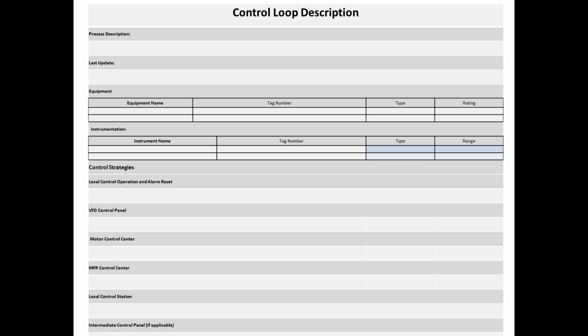The motor control center may not have anything else other than a power switch, but you say that in order for that piece of equipment to run, the power switch needs to be energized. Maybe there's an overload reset button on the bucket at the motor control center, so you would want to describe that reset switch and what it's used for.